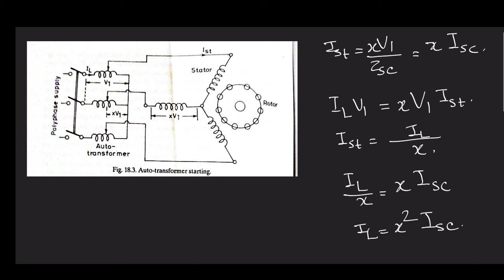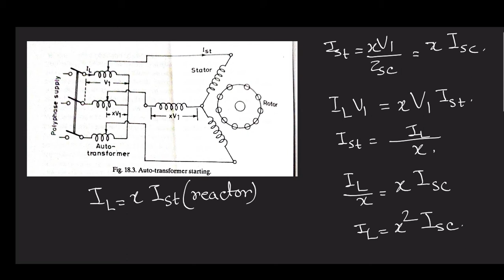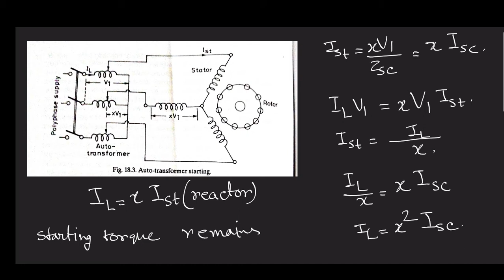so see, previously our IL was, for auto transformer it was X times I_ST when we consider reactor. Now it is reduced by another additional factor, another x, and x, being a number that is less than 1, always offers attenuation. But if we compare the starting torque, we will see that starting torque remains same for reactor and auto transformer.